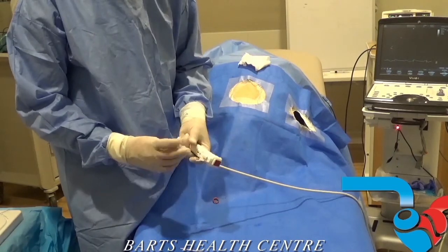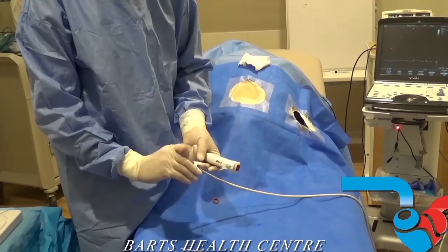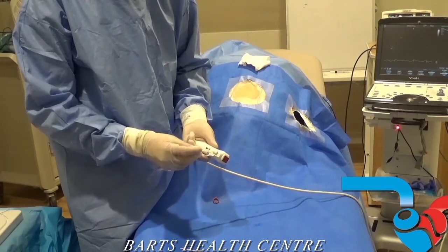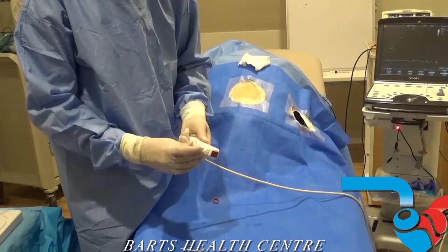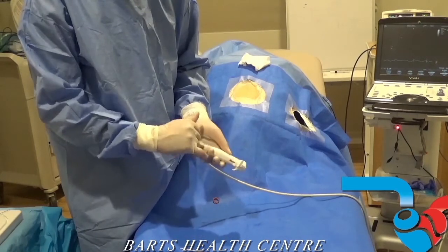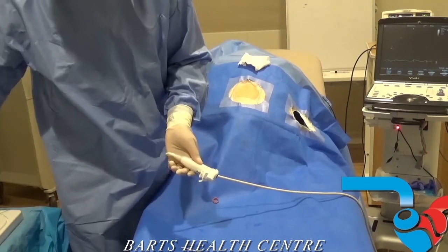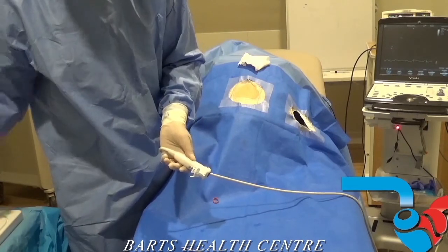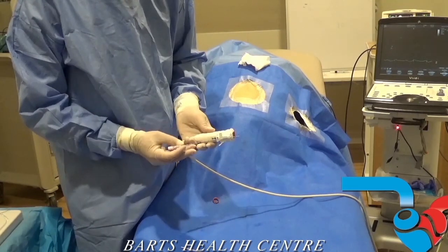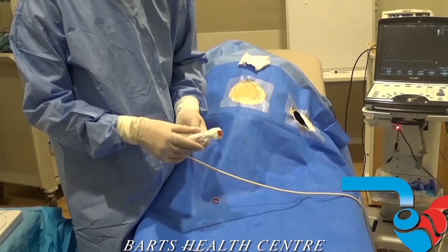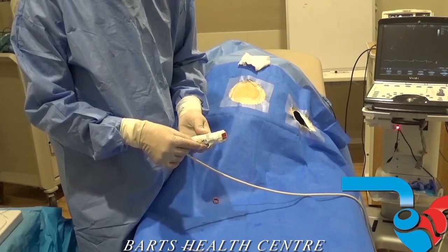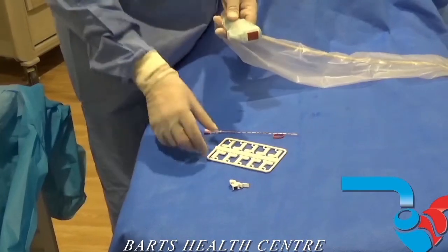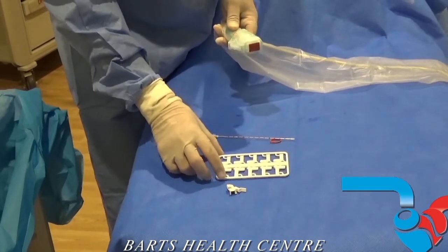After that we have a sterile portion which comes in a sterile pack, which is disposable, which comes without an insert, which then clips on over the sterile bag onto that needle guide, and then it comes with a range of inserts. This one's a 16 gauge one, but we'll need a 14 gauge one, and that just then slides in, and then the needle can be introduced, and the needle is always in the plane of the ultrasound beam.